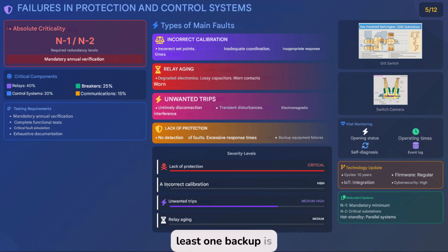At least one backup is mandatory, at least 2 backups are ideal in sensitive facilities, and a hot standby configuration is a safeguard against sudden failures. In short, these systems don't fail frequently, but when they do, the impact can be devastating. Investment in maintenance, redundancy, and upgrades is not a cost, but a barrier to much greater losses.